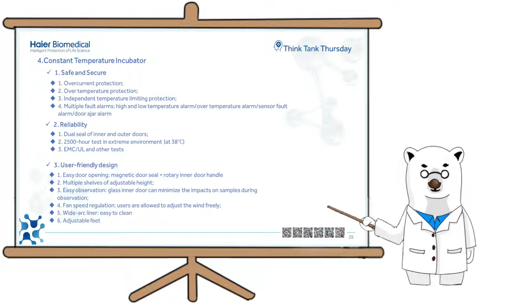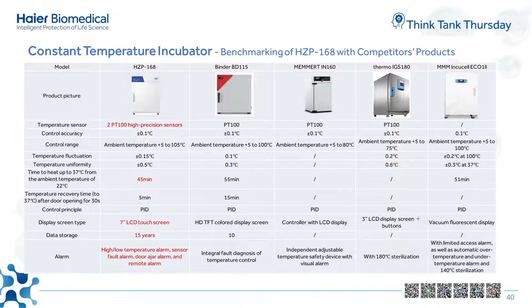Compared to competitors' products, our product HZP-168 has 2 PT100 high-precision sensors and takes 45 minutes to heat up to 37 degrees from an ambient temperature of 22 degrees. And we have the 7-inch LCD touchscreen. It's very easy to control the product and very easy to see the graphs and the data. Also, we have 15 years data storage and high-low temperature alarm, sensor fault alarm, door alarm, and remote alarm.